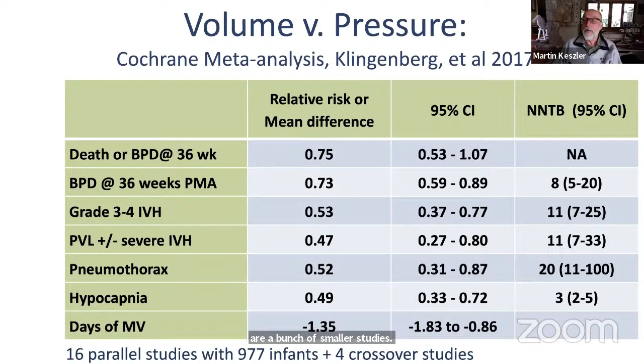I want to draw the contrast between volume-controlled ventilation that's used in the pediatric and adult intensive care units and volume-targeted ventilation. They're not the same, although the literature is sometimes confused about that point. And the problem with volume-controlled ventilation on devices like the Servo-i in particular, and this newer Servo-n is a little bit better in this instance, but basically what's controlled with volume-controlled ventilation is the volume of gas that's injected into the proximal end of the ventilator circuit.